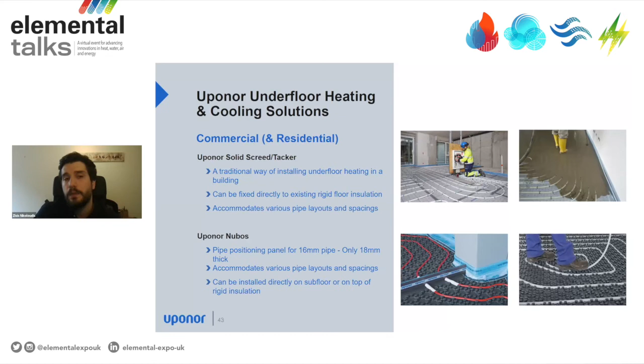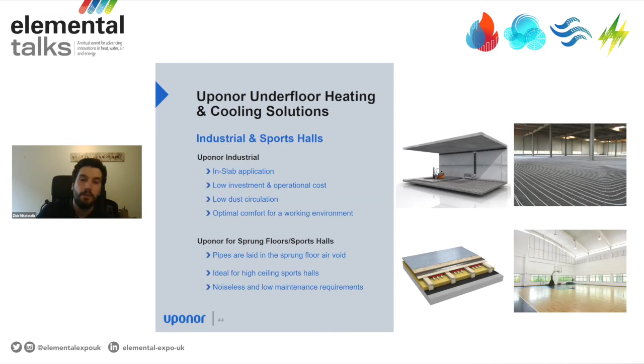Another very good application of underfloor heating and cooling systems is industrial and sports hall projects. The main benefit for these types of systems is that primarily they're installed in areas that have high ceilings. Therefore, underfloor heating is ideal as it creates a thermally comfortable environment in an occupied area of 3 meters high without having to warm the whole air void above this level. Especially when it comes to industrial applications for warehouses and manufacturing facilities, this is very important for the well-being of the occupants, as the radiant solution reduces the dust circulation, and the system comes with low investment and low operational costs.